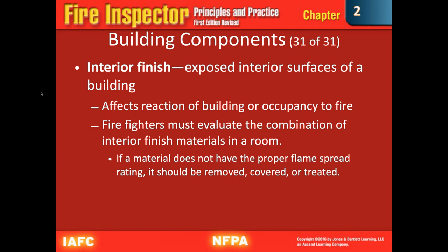So if you walk into a room where the life safety code for that particular building occupancy use says that these things need to be met, and you come in there and they've got church curtains hanging and stuff stacked to the ceiling and all these things, it doesn't matter what the room's made of, the contents are going to burn so fast and so bad that it renders all the safety mechanisms of the room completely useless. These are the things you want to watch out for. So don't discount what's hanging on the walls. You got to consider everything inside the room. Foam plastics or carpeting should be a red flag to fire inspectors, just to kind of cap that off.